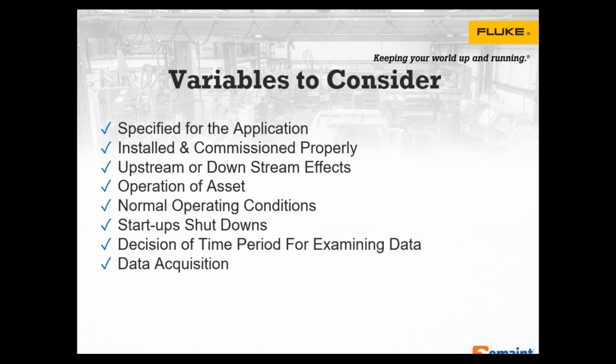These are things you definitely need to understand about your asset: the sample rate. Is this data coming in every minute, or every second? And if it's coming in every minute, am I missing things I should be seeing in my process? So this is really an important point: understand the sample rate and how often it's being refreshed.